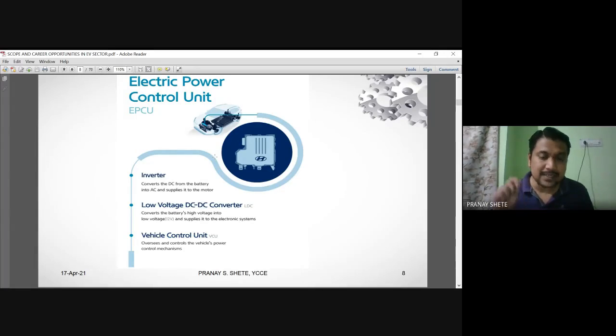What do you mean by specified? It is the rated voltage at which your motor will run. If it's an induction motor, the required voltage is 3-phase voltage - 420, 415, 440 volts - depending on the full load rating of your motor, the rated parameters printed on the motor. You decide that rating, and the EPCU will take care of this magnitude of voltage, because the motor always runs at the rated voltage. Current may vary depending on the load applied on the motor.